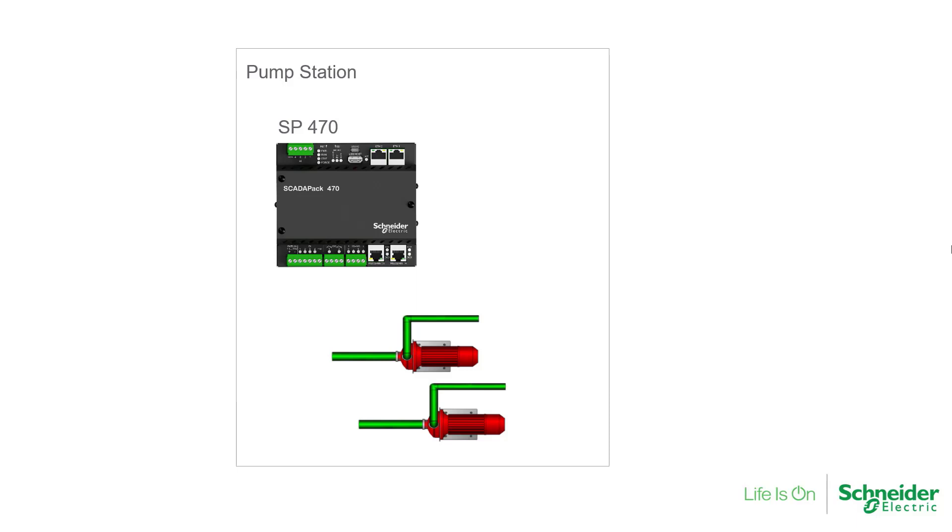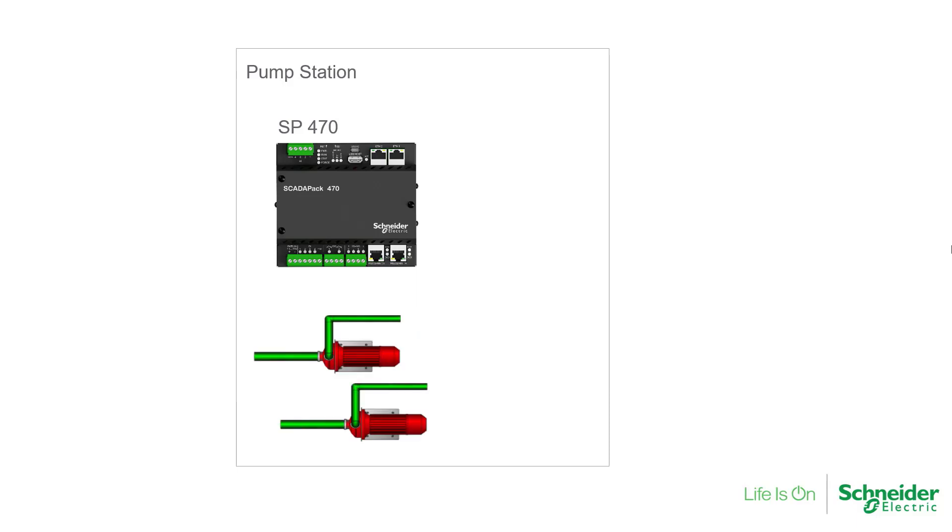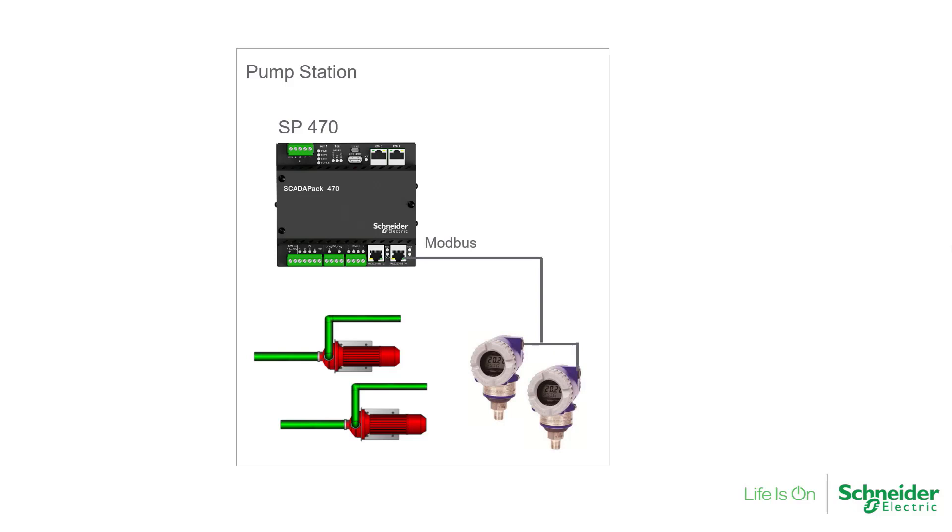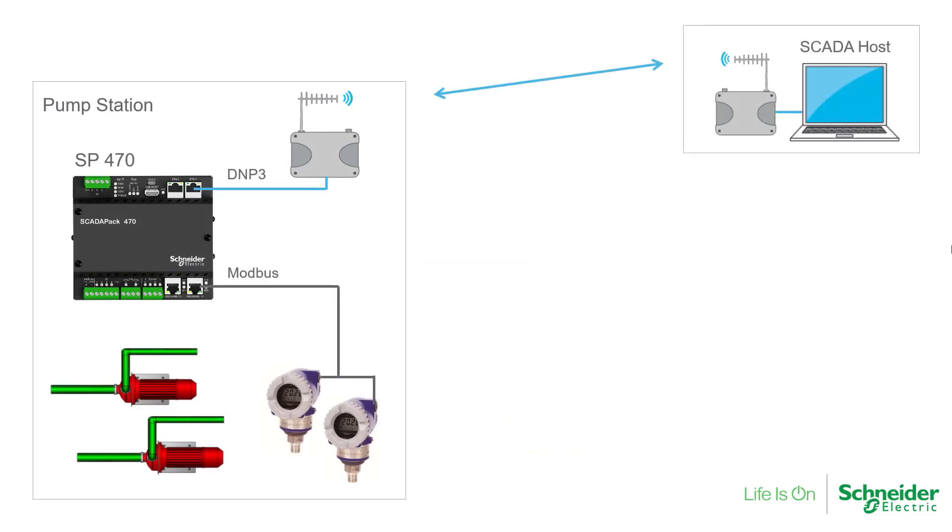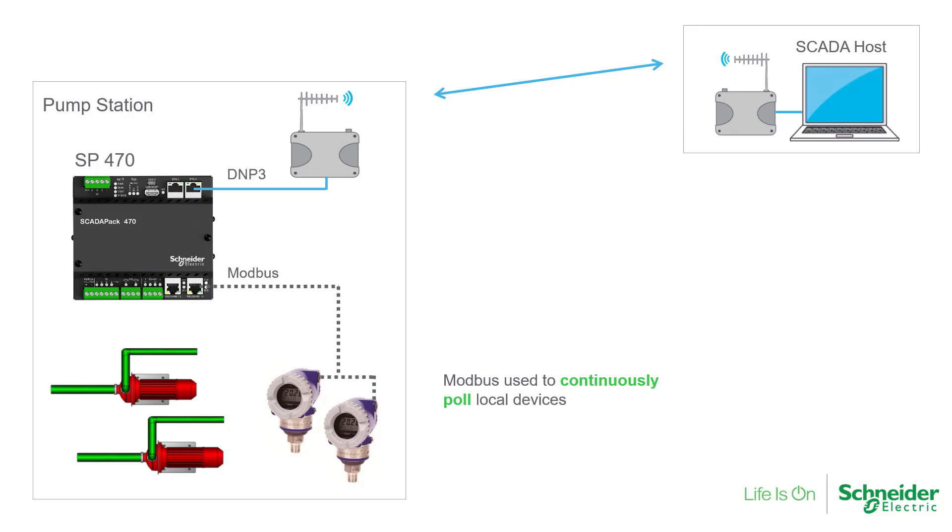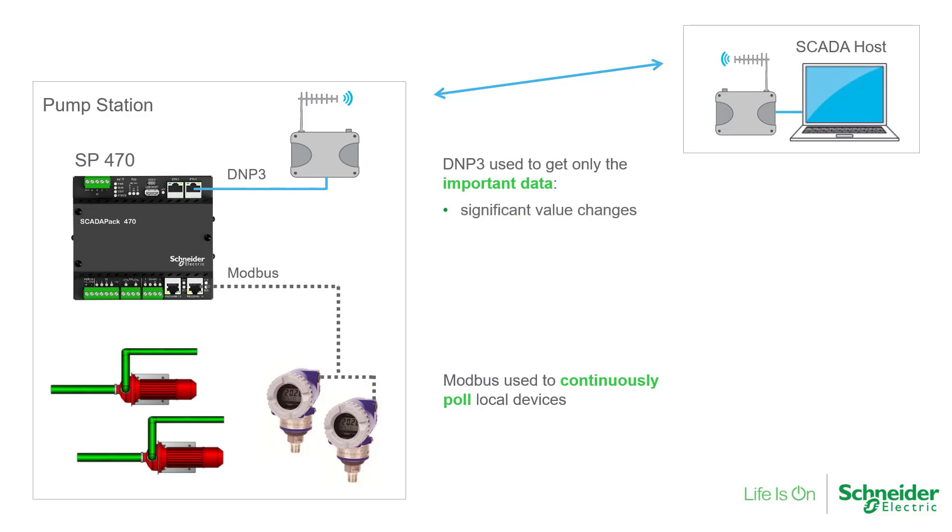Our application will look at a pair of pressure transmitters. These devices may be multi-dropped over one or more RS-485 serial ports on the RTU. The RTU will continuously poll data from all Modbus devices, but it will only report important data changes to the SCADA host using DNP3. The important data will consist of just the significant value changes and any spikes or alarm limit exceedances.